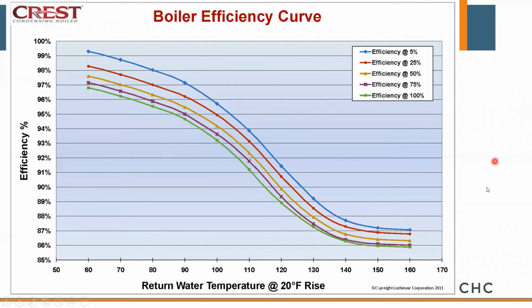We'll get to that in just a minute. Now, the shame of this is if you put this boiler into an old school system, meaning a system that was designed at 180 degrees out and 160 back on return, you'll notice that this boiler is only going to run 87% efficient, not 99% that you thought you might get. Okay, so it's based solely on return water temperature and firing rate.